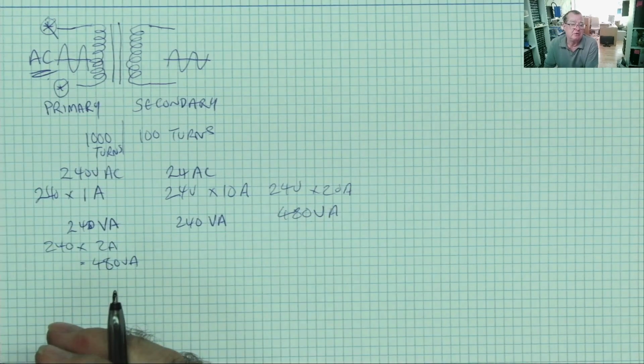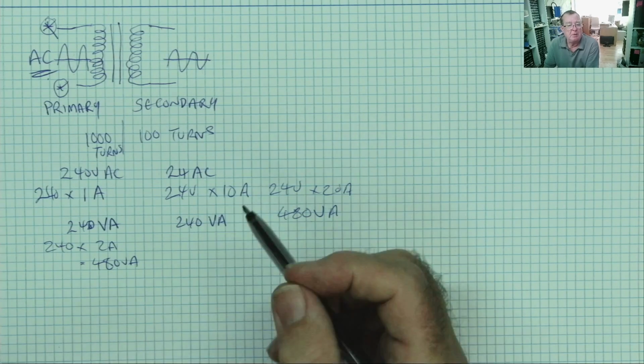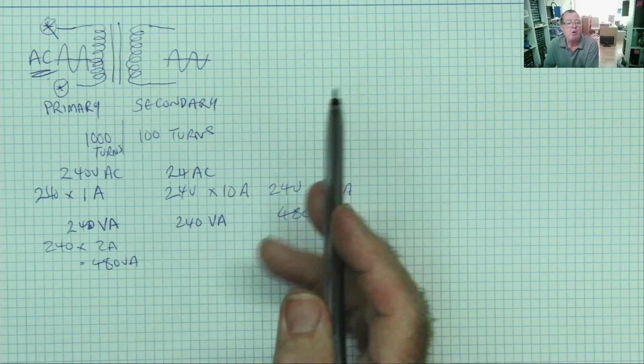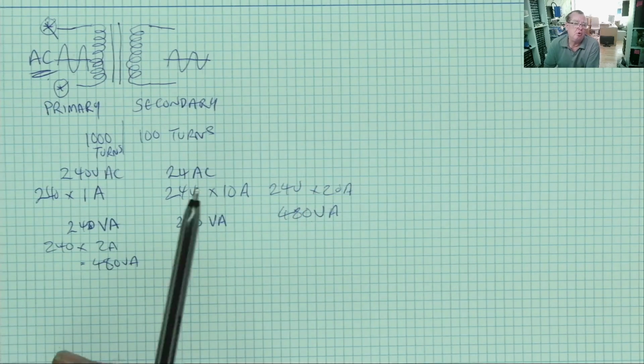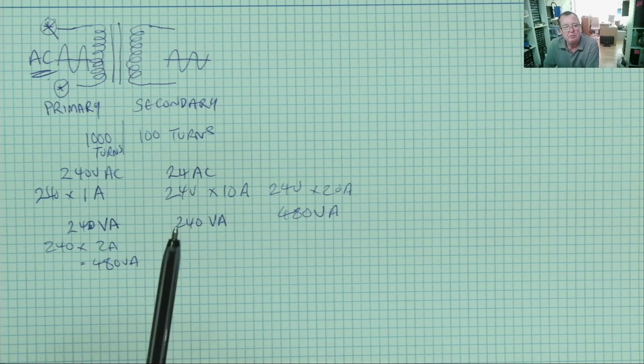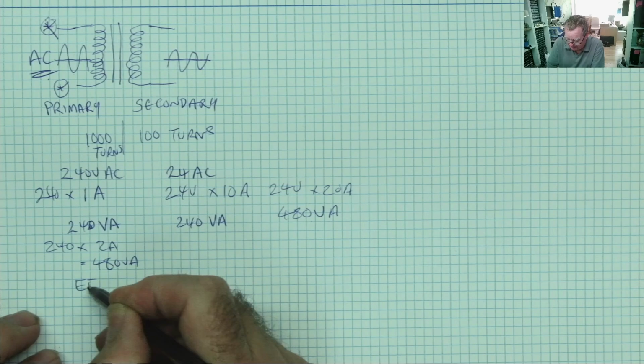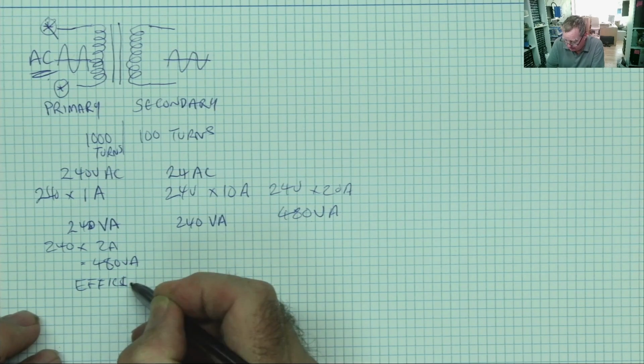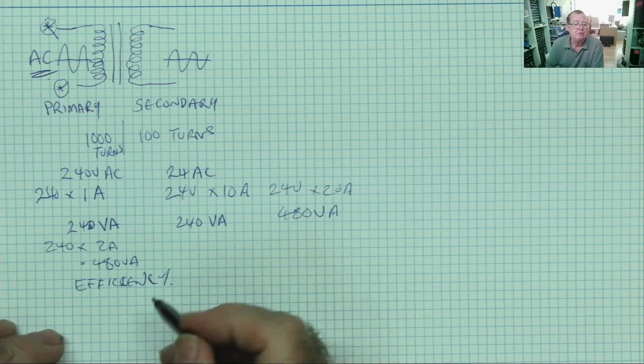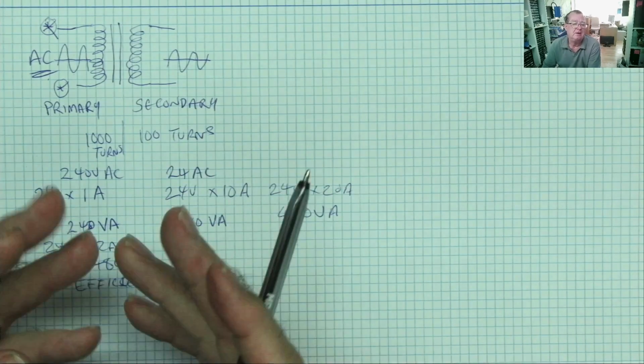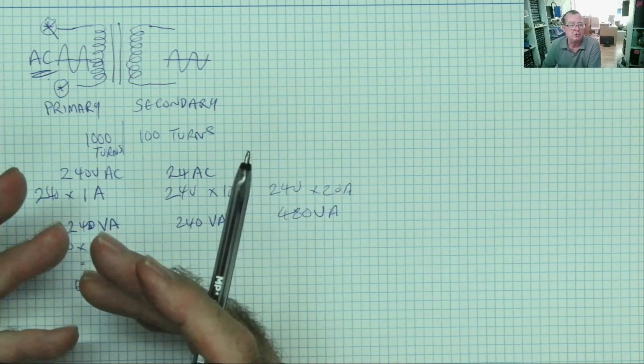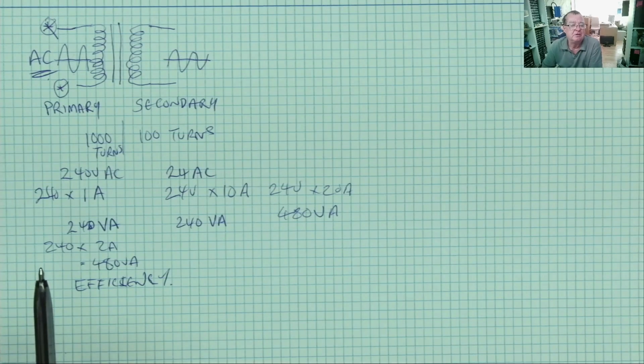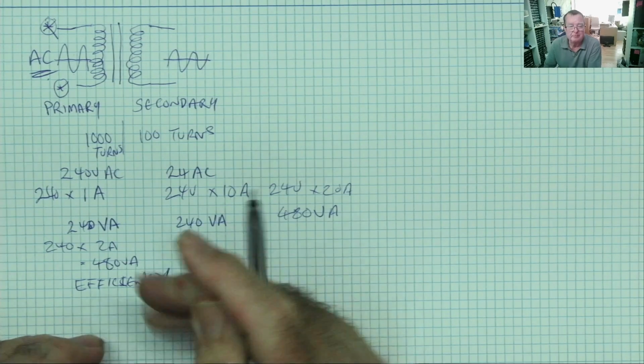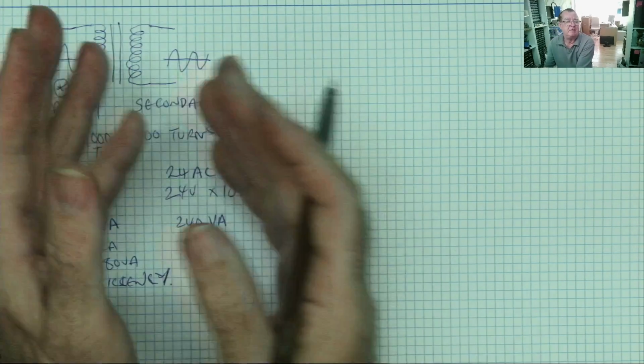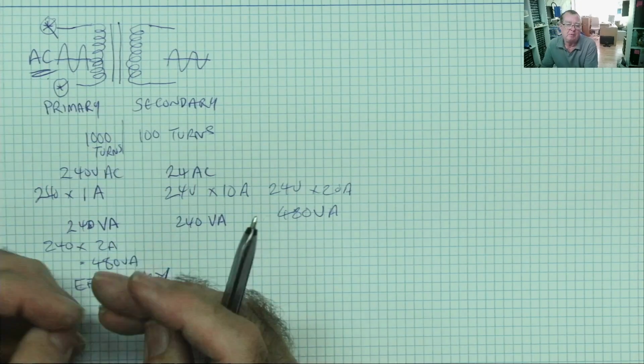It always has to balance. If you reduce the current you are drawing, the supply current will reduce. So if you put no load on the secondary, will you get no current in the primary? No, you won't, because there's an efficiency of this. So the efficiency is basically due to the fact that this coil of wire, although it's an inductor, also has some resistance, and it will pass some current even if you're drawing no current on the secondary. So you will not have 0 amps going in if there's 0 coming out. You'll have some going in and nothing coming out.